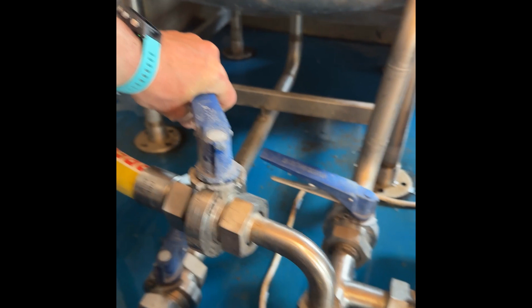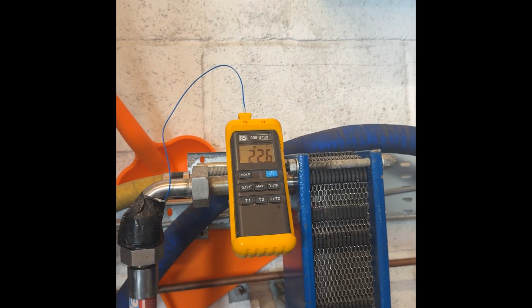If I go round now and start my transfer pump, I can hear the pump running over here. I can pop this just here, that outlet just there. And now by opening this, I can see it starting to pump. I know it's pumping because I watch this temperature here, and it will suddenly start jumping up. Open this a little bit more - so I can see there's flow coming out over here, look.